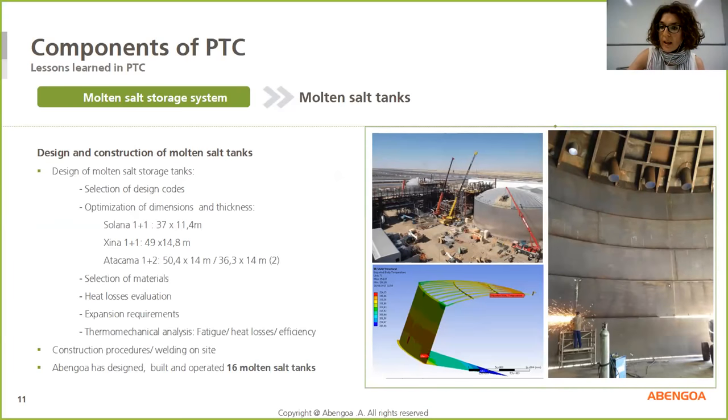In this sense, we must talk about the design and construction of the molten salt tanks. The design must take into account the thermal expansion requirement, the thermal behavior of the tank, the thermal losses allowed, and the thermomechanical validation of the system for its lifetime. And during the construction on site, welding procedure validation, welding execution, and an intensive inspection are mandatory.